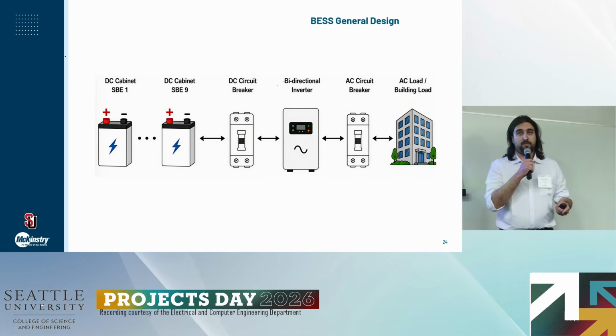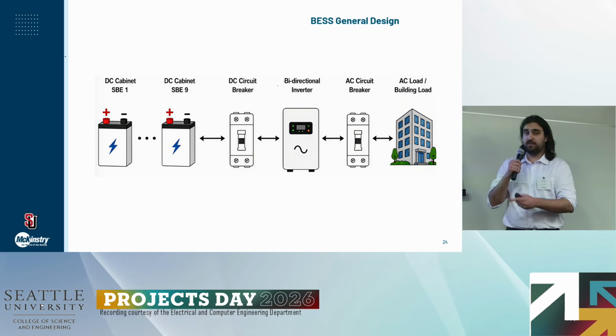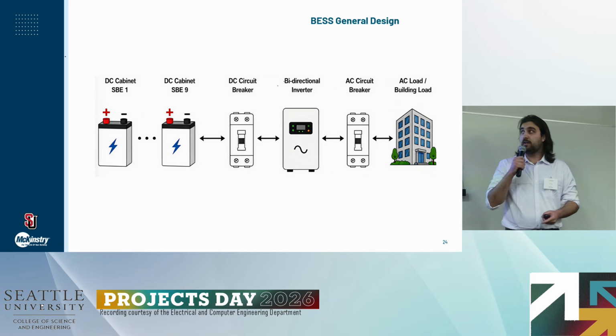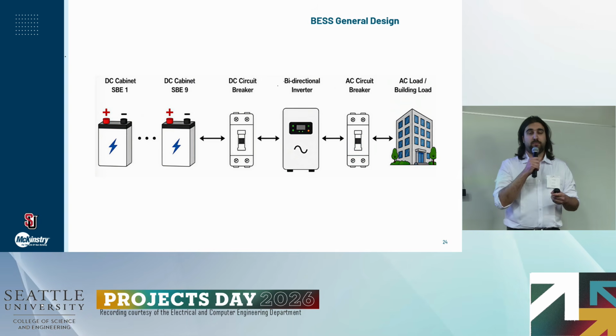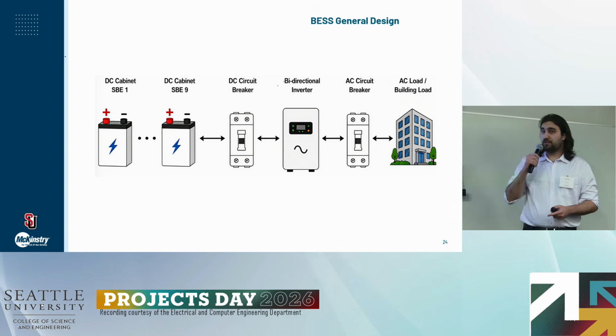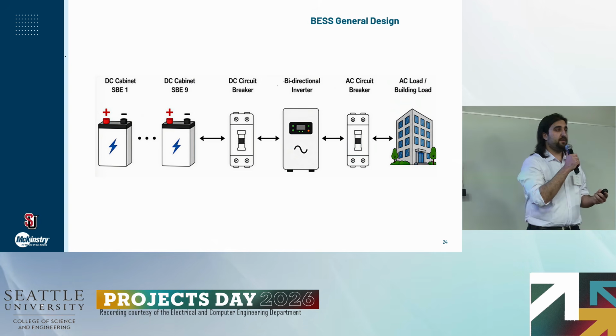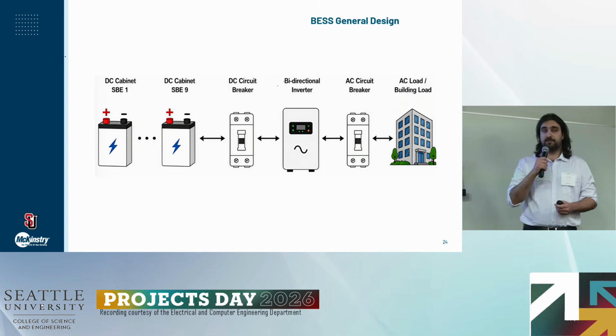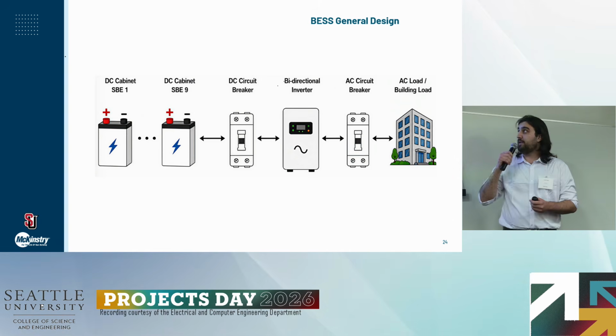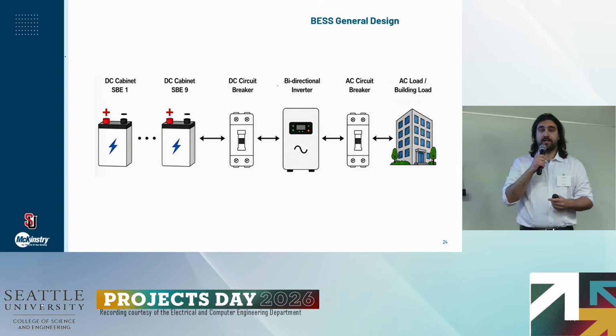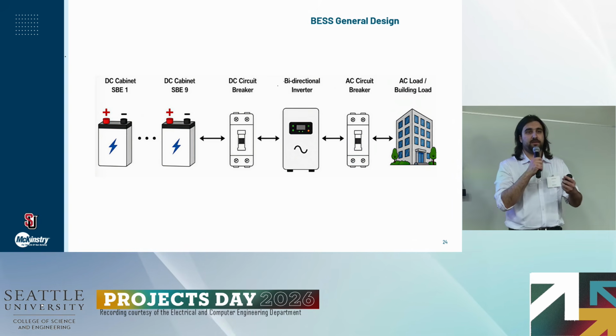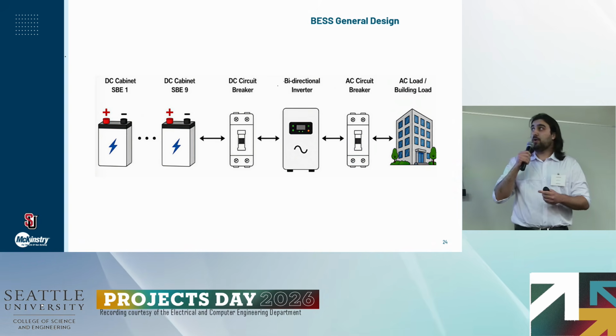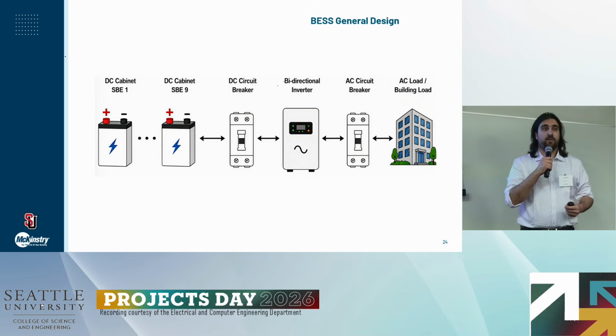The diagram shows the proposed battery energy storage system connection using 9 batteries in series. A series connection was chosen because it provides higher DC voltage while reducing the current and cable losses, making the system more efficient. We have 2 circuit breakers that protect the batteries and the building, and a bidirectional inverter that converts direct current to alternating current when the battery is discharging, and alternating current to direct current when the battery is charging.